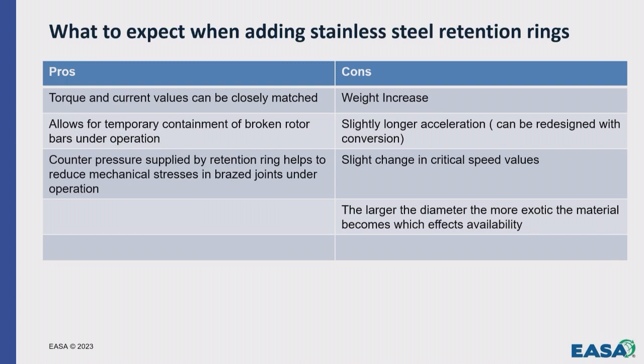The counter pressure of the rings helps significantly reduce the stress on your brazed joints, because without that compression you don't have all the forces acting when it expands out while running at 3,600 RPM. But the cons, and there's always cons, is that whenever you go from aluminum to copper, you have a weight increase on the rotating element. Of course, if you just add stainless steel rings, you're also going to have a slight increase. And as we all know, if you add weight to the rotor, even though your torque and current characteristics aren't going to change, you will see a change in your rotor inertia.